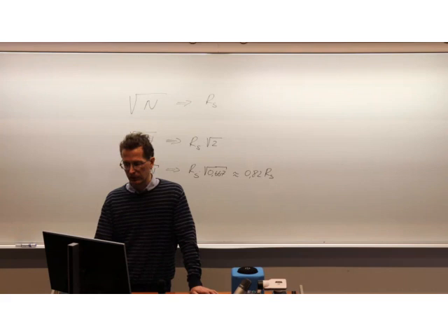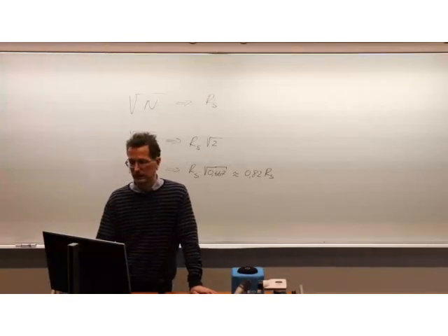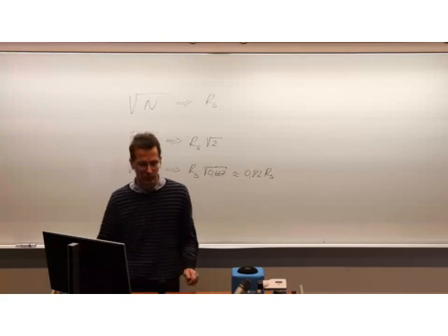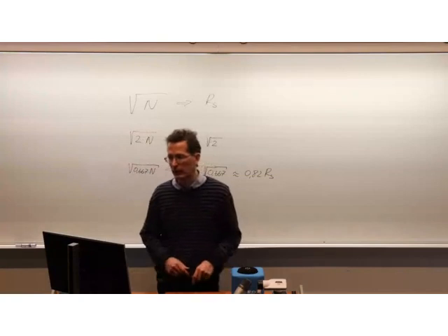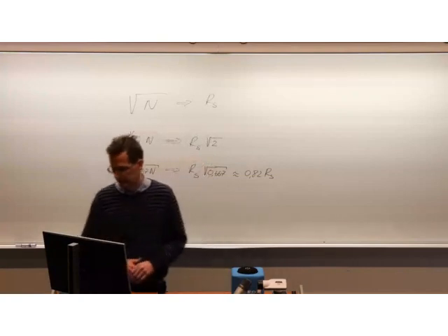And the number of theoretical plates is similar, just without this square root, quite understandably. And pressure is 1 divided by particle size squared. So this helps to estimate what the pressure would be in the column if we use a column with a smaller particle size.